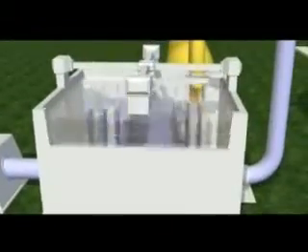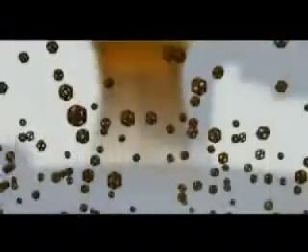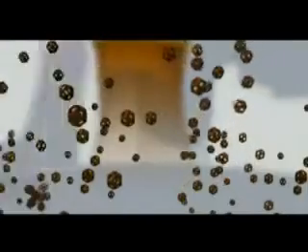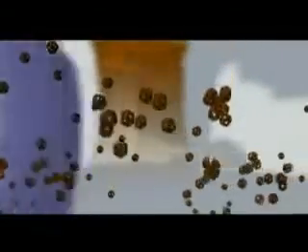At this stage, there are still some fine pieces of matter suspended in the water, along with colour and bacteria. We add a precisely controlled amount of a coagulant like ferric or aluminium sulfate. This reacts with the material in water, making it all stick together to form what's known as floc. To make this flocculation happen, water and the coagulant have to be mixed together very quickly and thoroughly in a special device called a flash mixer.